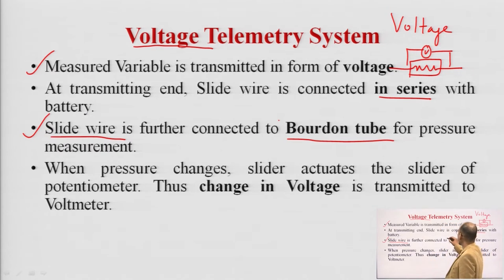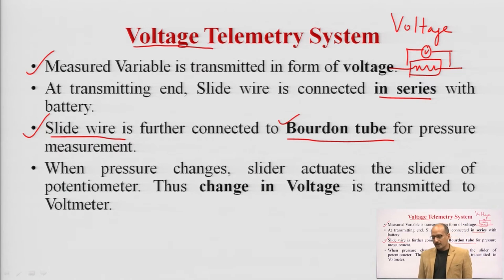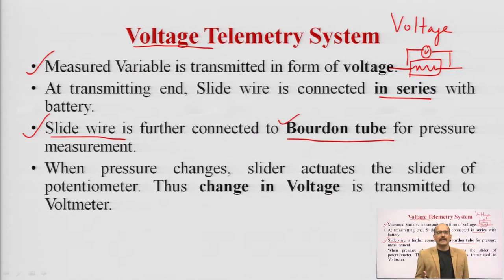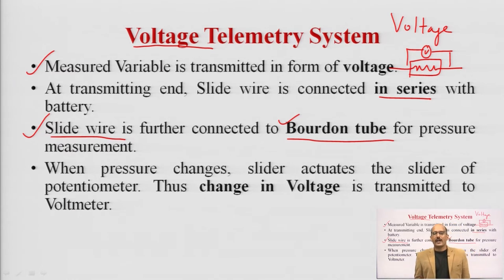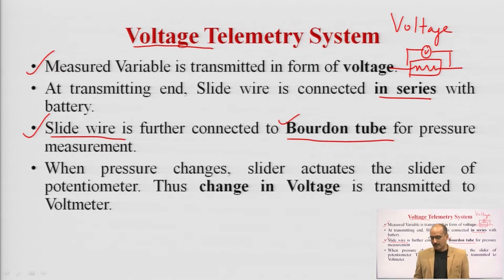Here I am taking the example of a Bourdon tube, though it is not always necessary — you can use any type of transducer or sensor as per your requirement. For example, when measuring pressure at a remote location, we use a Bourdon tube. The Bourdon tube is made of elastic material which can expand or contract as per changes in pressure. When the pressure changes, the slider actuates the slider of the potentiometer, and the change in voltage is transmitted to the voltmeter.